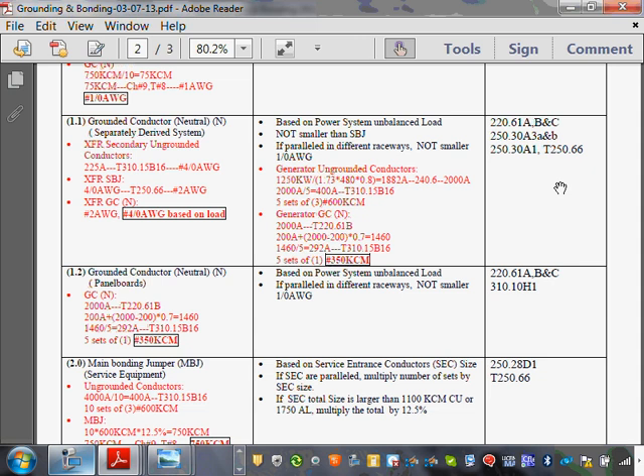So in this case, I pulled full neutral. Can you see my grounded conductor here? I took 225 amp, and my system bonding jumper is 2, so my grounding conductor is 2. Now, the code says, guys, this neutral cannot be smaller than the system bonding jumper. So I can't pull less than number 2 even if I tried. It has to be at least number 2. But I like to pull full neutral for this system. Any comments, guys, on why we pulled a smaller neutral for 480/277, 208/120? I could have done number 2. The minimum is the system bonding jumper.